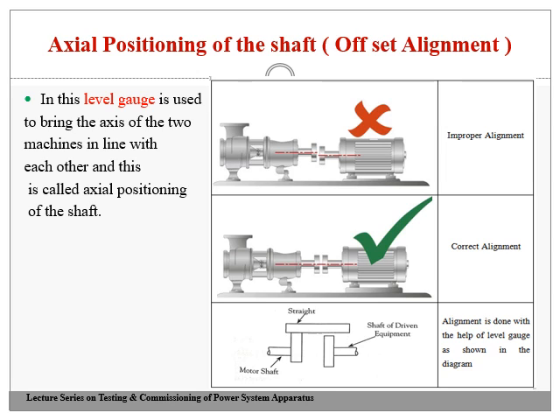How to raise that? That's why the shimming process came into the picture, which we studied in the last class. I'll raise the height of this machine by the shimming process, so that axial positioning can be obtained. By the shimming process, I can raise this one. That's why it has come into the picture. This way, the axial positioning of the shaft can be done. This is the first method.